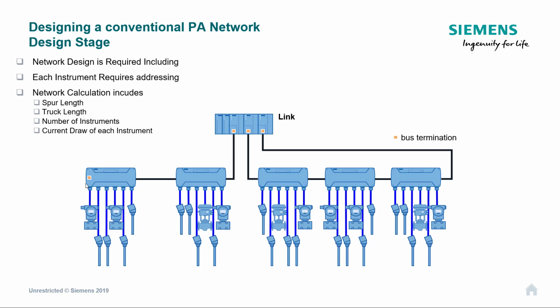And we also have to make sure that on our network design drawing we show all of those items, like cable lengths, positioning, and also on that drawing, ideally we want to know the address of each one of these instruments, because Profibus PA devices are by default shipped with an address of 126. Of course, you can change that. A lot of manufacturers like Siemens, you can, for instance, purchase it pre-addressed and pre-tagged with a stainless steel label on there as well. So as long as you put it in the right place, everything will be okay. But normally, like I say, by default the address is 126. So that's the design stage.